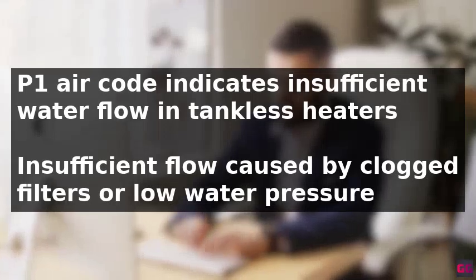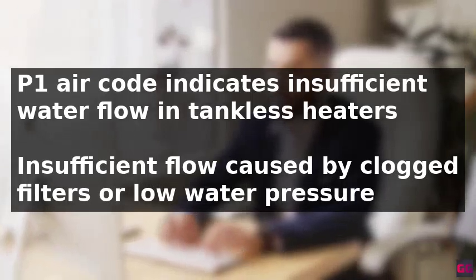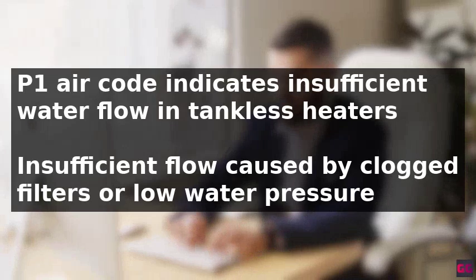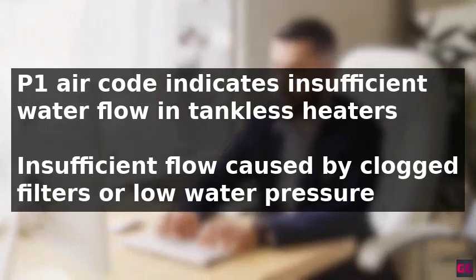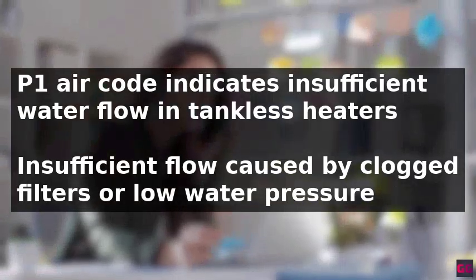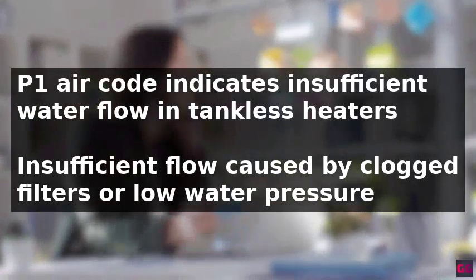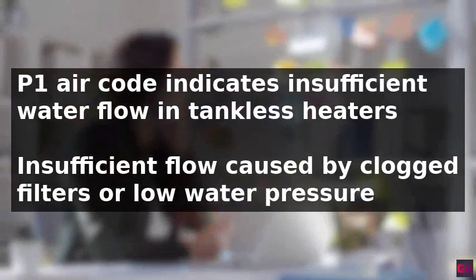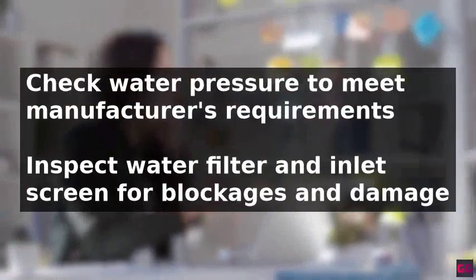The P1 error code on a tankless water heater indicates that the heater is not operating normally due to insufficient water flow. This issue can be caused by a clogged water filter, a blocked circulation line, or low water pressure.